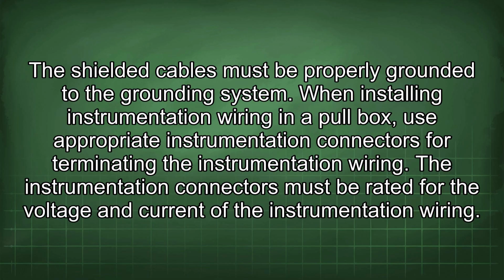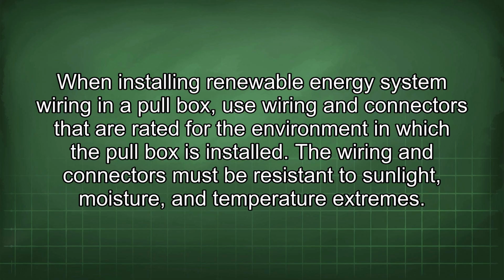The instrumentation connectors must be rated for the voltage and current of the instrumentation wiring. When installing renewable energy system wiring in a pull box, use wiring and connectors that are rated for the environment in which the pull box is installed. The wiring and connectors must be resistant to sunlight, moisture, and temperature extremes.